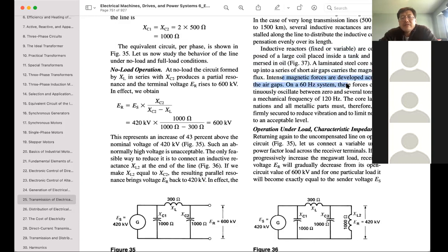Intense magnetic force develops across the air gaps. It will oscillate at 120 Hertz. So this inductor will be under tremendous mechanical force at 120 Hertz. So the coil must be firmly secured to limit the noise to an acceptable level.